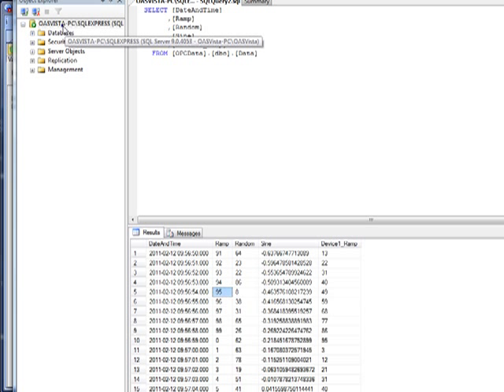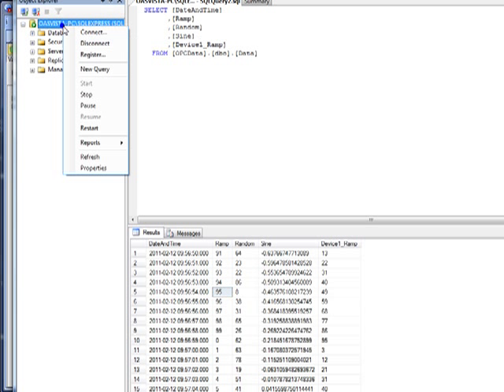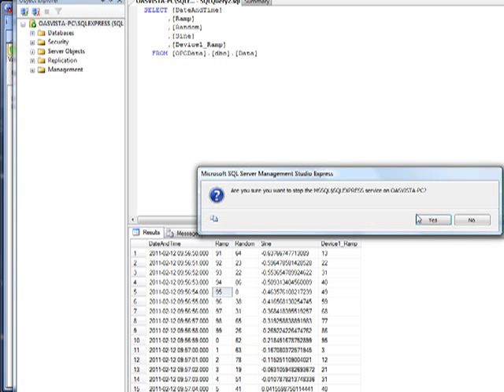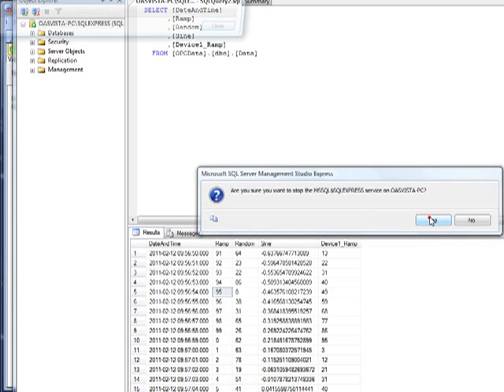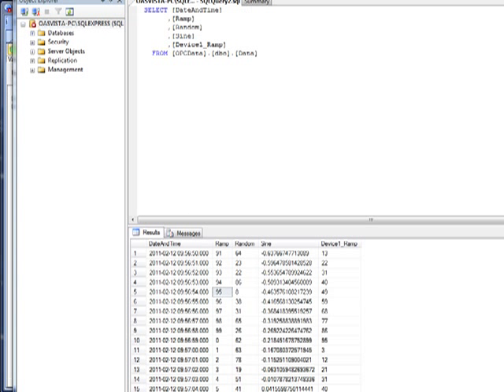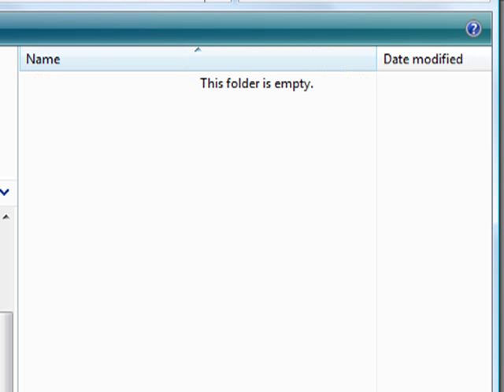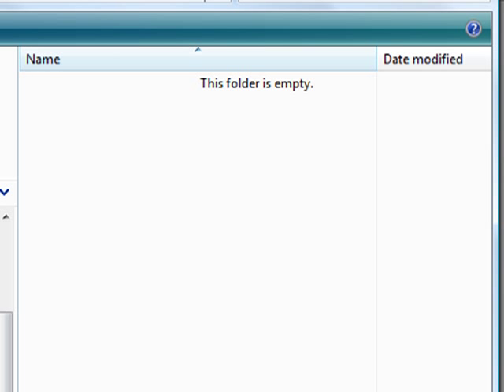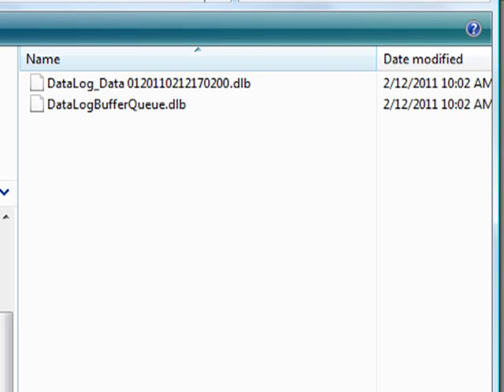So let's demonstrate that. What I'll do is I'll actually stop the database engine here using the SQL Server Management Studio. I'll go into the directory that I am currently buffering that data to. I had a directory called buffer data. Now we have our first buffer file already into that system and we see that for every minute now we'll have a new file that will be logged into this. So even though our system is currently unavailable to write the information to the database engine, we are still able to connect to the OPC server locally and we're able to still cache that data and buffer this now to the hard disk.